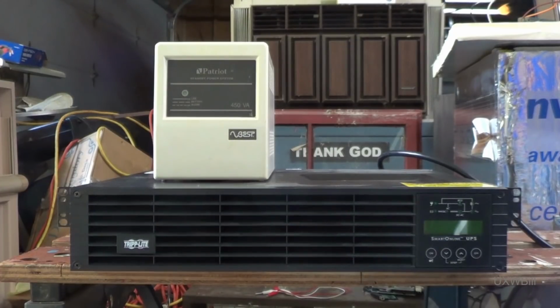A line interactive UPS also typically has the capability to adjust low or high line voltage, sometimes only one or the other, without actually having to switch over to the inverter and head for the battery, which only has limited runtime. And then there are uninterruptible power supplies like the one you see below, the black Tripp Lite, that are referred to as online or double conversion uninterruptible power supplies.